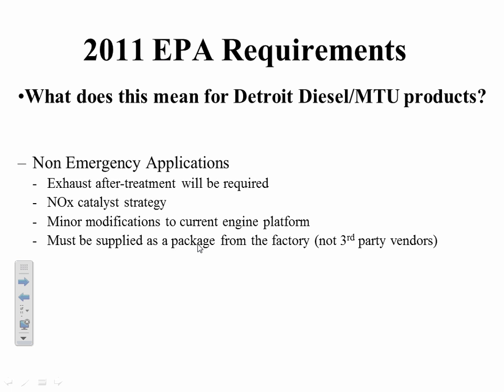There are two ways we can address this issue. We can either have a factory certified engine on new equipment, or the EPA will also recognize a third-party vendor, and if they can get the emissions in line, and it has to be tested, they'll offer what they call EPA compliant. So factory certified by the manufacturer or EPA compliant by a third-party vendor.